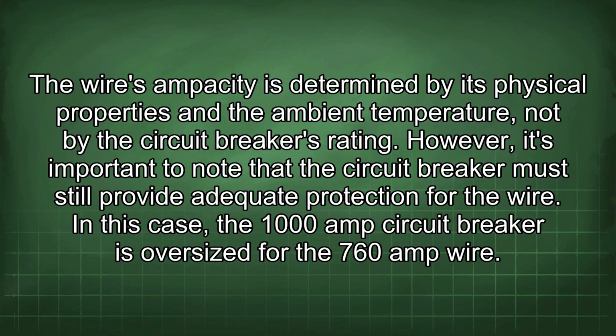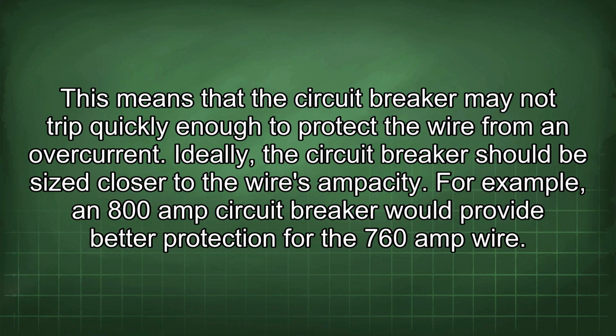However, it's important to note that the circuit breaker must still provide adequate protection for the wire. In this case, the 1000 amp circuit breaker is oversized for the 760 amp wire. This means that the circuit breaker may not trip quickly enough to protect the wire from an overcurrent.